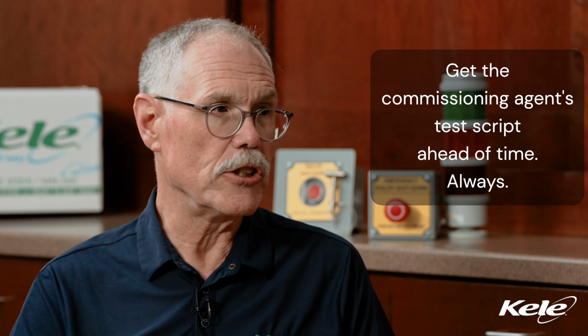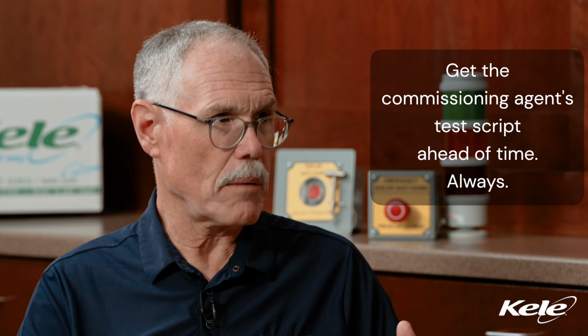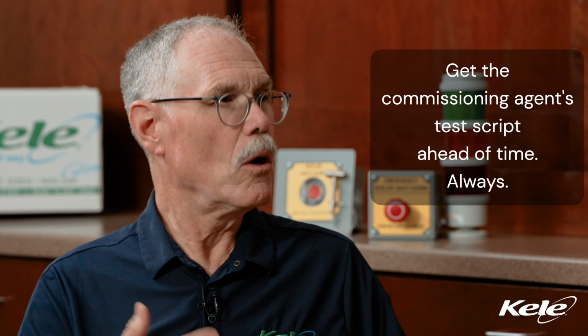Another thing that shows up often is the contractor never gets the commissioning test script ahead of time, so you don't really know what the commissioning agent is going to ask you to do on site. Every contractor should always get the commissioning agent's test script ahead of time so you can do the testing needed and make sure the system passes commissioning. I've seen instances where there's one line of a test checking whether it's exactly on the sequence of operations, and I'd have to incorporate that just so there's no problems on commissioning day.